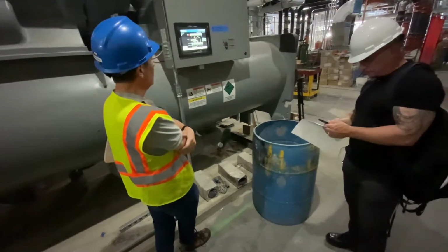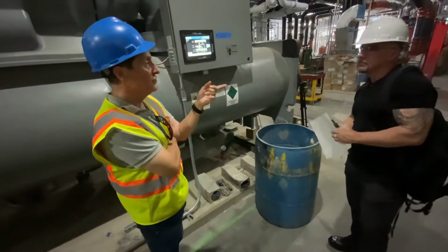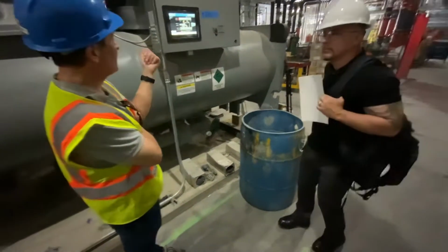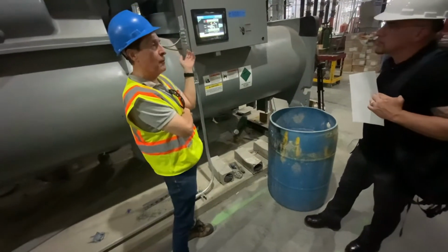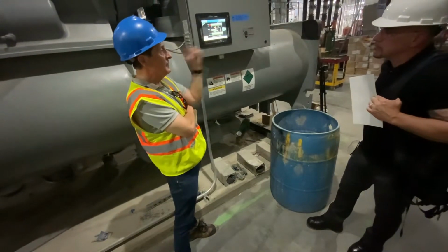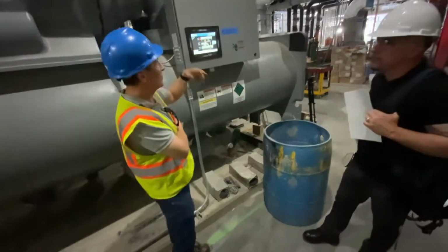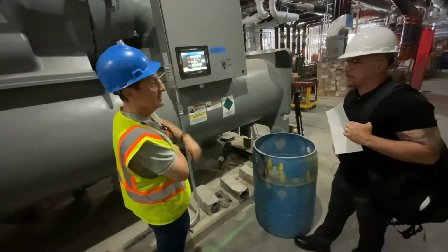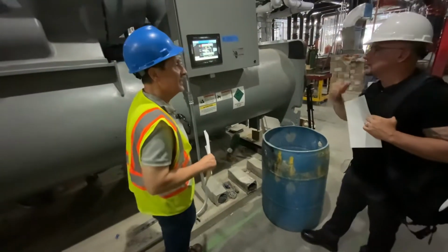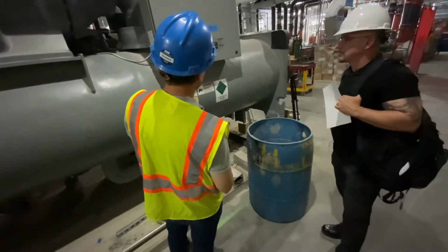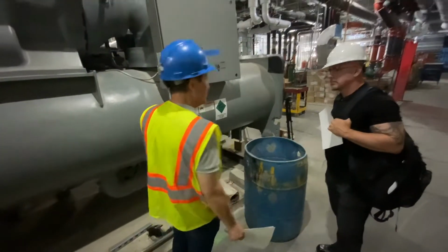They're actually supposed to be doing a head pressure control logic on this job, which they're not set up doing correctly yet. It's supposed to look at the output of the chiller. We have an output that tells the BMS what speed to run for how much water to flow through the chiller, to create the pressure differential we need. So that output is supposed to be used. They didn't set it up that way for some reason, so they're working on it. The machine does have differential pressure sensors.